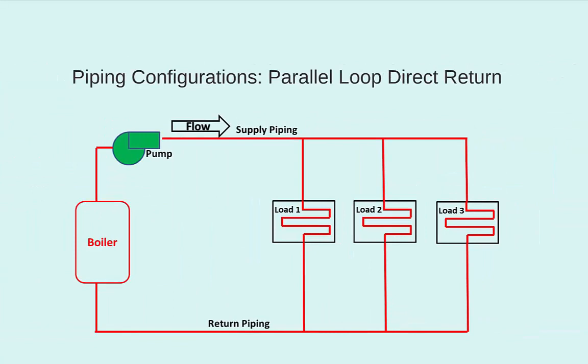We can also have a parallel loop piping configuration. In this configuration, there is a dedicated supply pipe and a dedicated return pipe. Each load pulls directly from the supply pipe, which means each coil is provided the same entering water temperature, and thus each coil has the same potential to expel heat from the hot water loop. There are two styles of parallel loop piping configurations. The first one shown here is called direct return, because as soon as the water goes through the coil, it directly starts its path back towards the boiler.